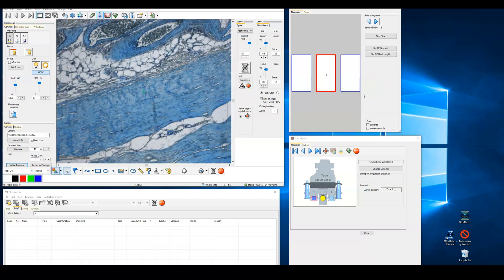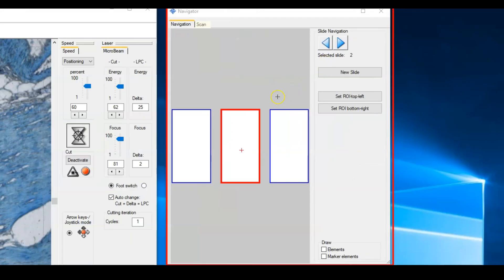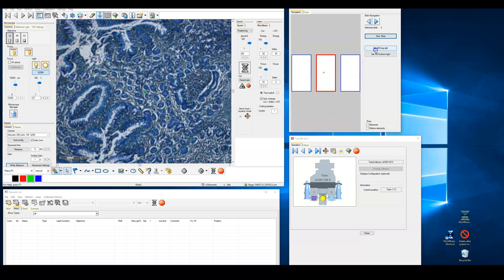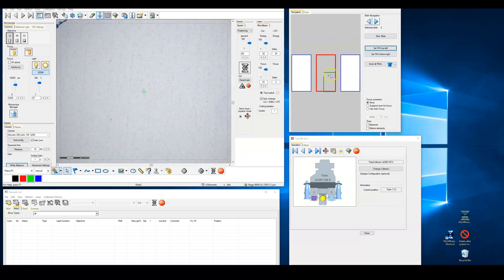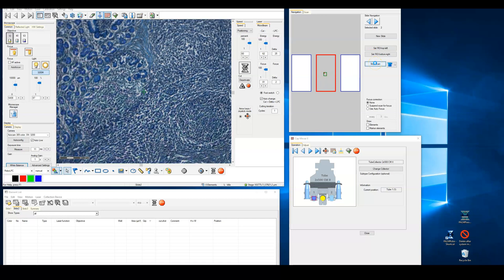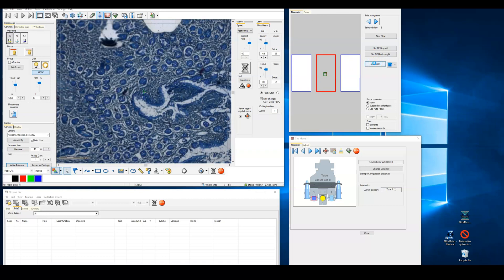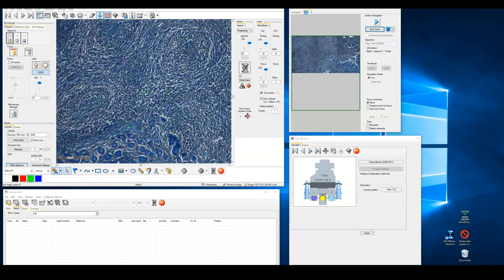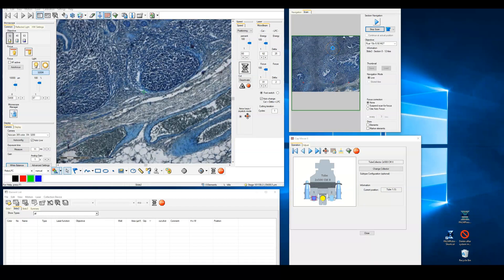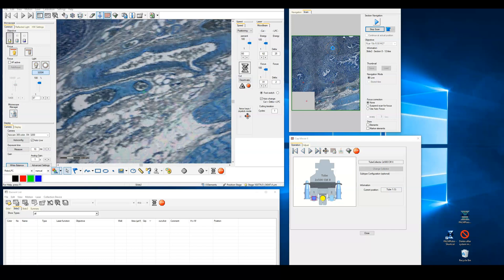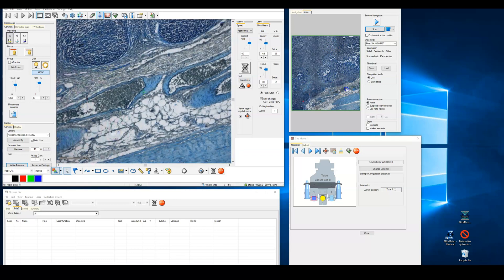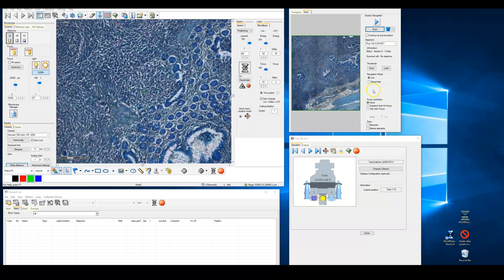Moving to the other windows, the navigation window allows us to move between samples by clicking on the slide of interest or by moving large distances within that slide. We can also generate a preview of our slide by defining the top left and bottom right of the region of our slide that we'd like to image and then scanning this region with the scan ROIs button. The result can be seen in the higher magnification under the scan tab. Here you can further navigate to a region of interest, but with the added benefit of being able to see your full tissue. If you're using a higher power objective or scanning a large region, you may want to enable the autofocus or manual focus pause before running the scan.